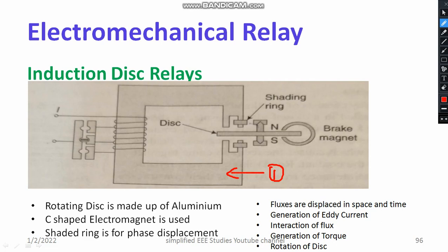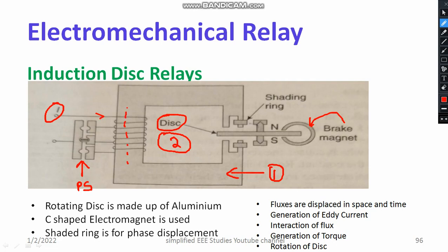Number two, we have an aluminium disc. Number three is your plug setting — I will explain what plug setting means. You can also see the operating current and a brake magnet. You can also see a shaded ring. The shaded ring produces a flux which is opposite to that of the main flux. As soon as you provide the current, there is generation of flux phi-1. Due to the shading, one more flux phi-2 is generated.